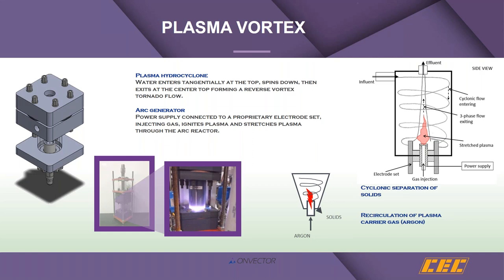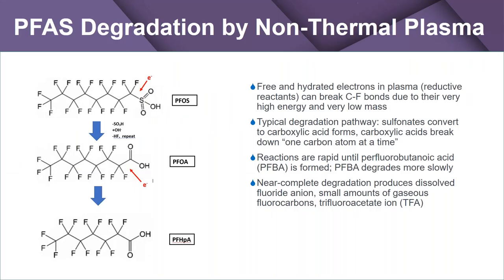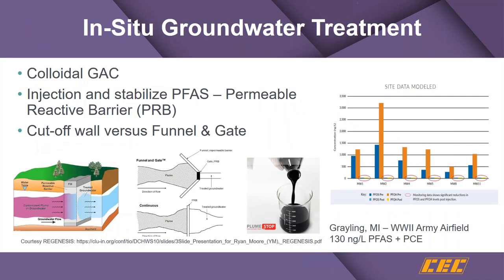Another company makes a slightly different plasma technology with a cyclonic flow of water and a plasma flame towards the middle, maximizing contact between the plasma and the liquid being treated. What we find is a sequential breakdown in plasma operation from longer chain PFAS down, with sequential degradation as carbons are removed. The longer chain carbons are more easily removed and can degrade to smaller ones, but smaller chain PFAS generally have a much longer retention life.